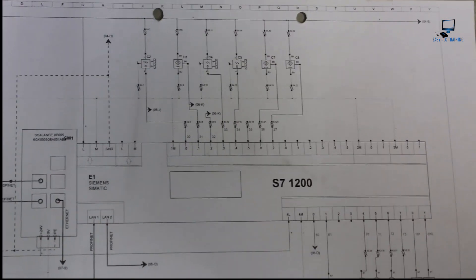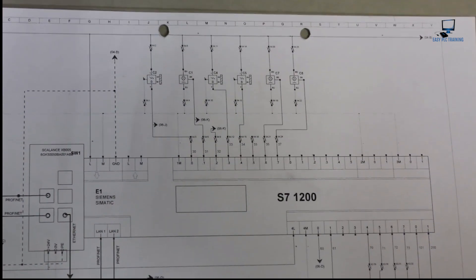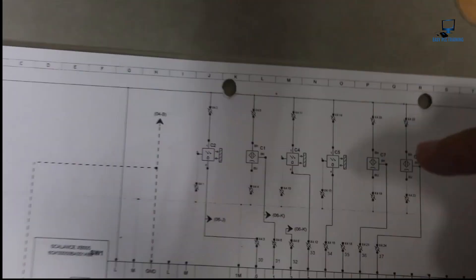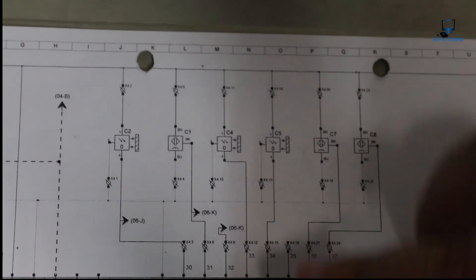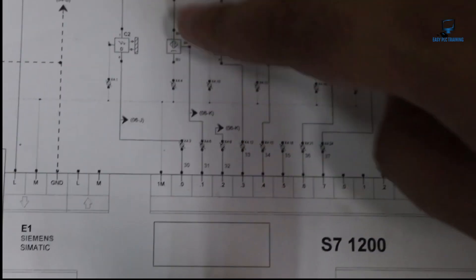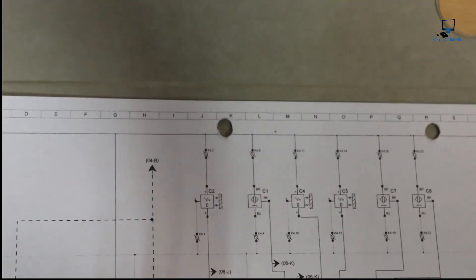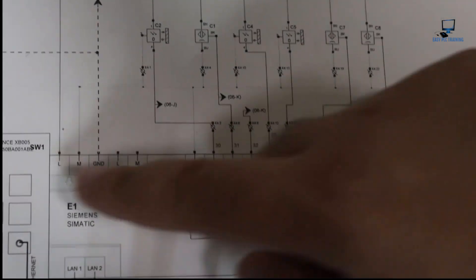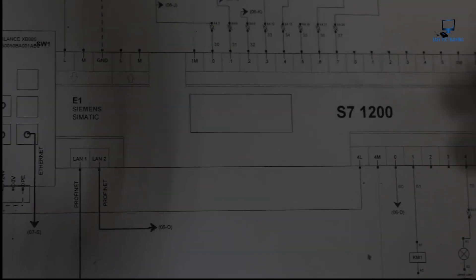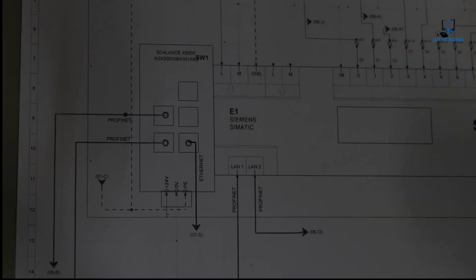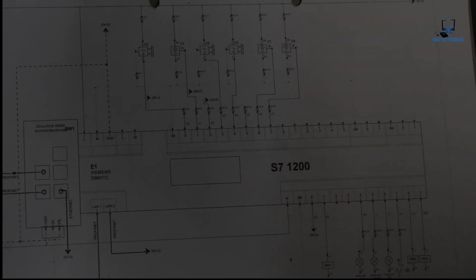We have checked our PLC panel, now it's time to explain the wiring drawing. I'm going to show you bits and pieces of that in our drawing. These are our inputs coming into our PLC — all inputs coming from the field — with 24 volt positive. The L+ positive and negative are coming from the power supply output side. On the output side, the PLC is going to our final control elements, actuators, and different industrial equipment. The PROFINET switch connects one cable from the HMI and another from the servo motor.